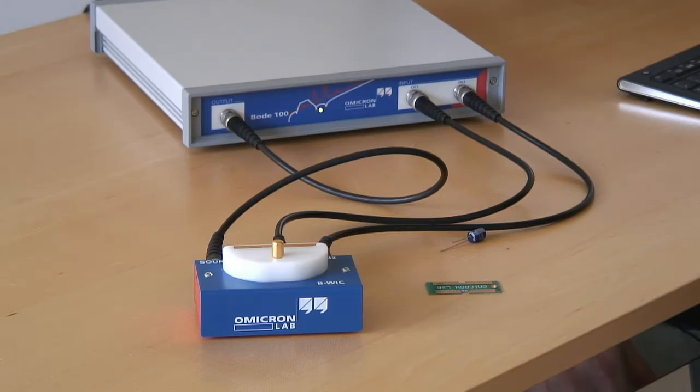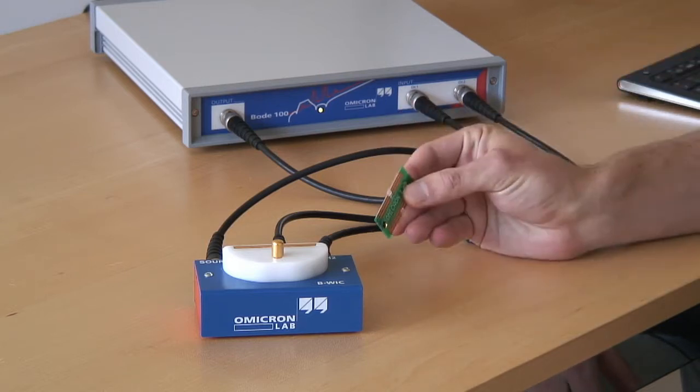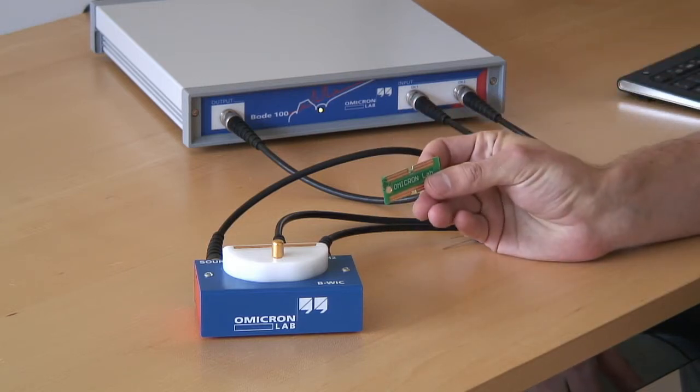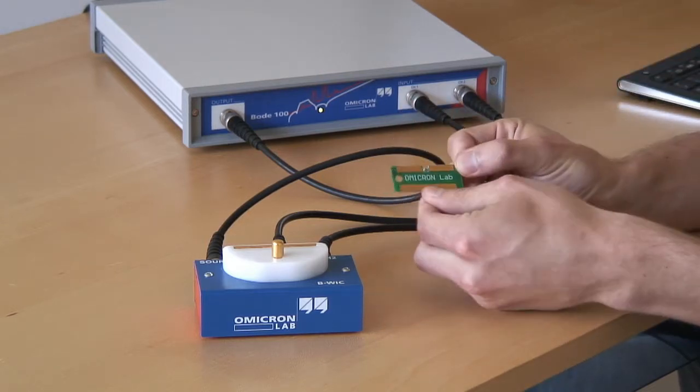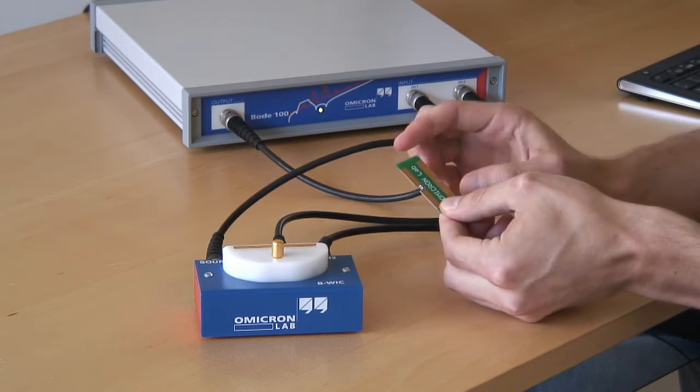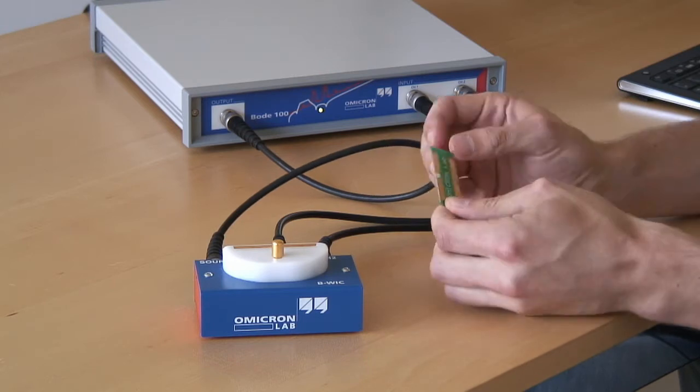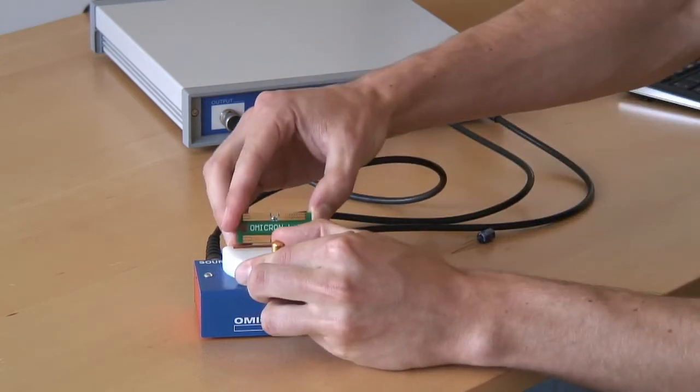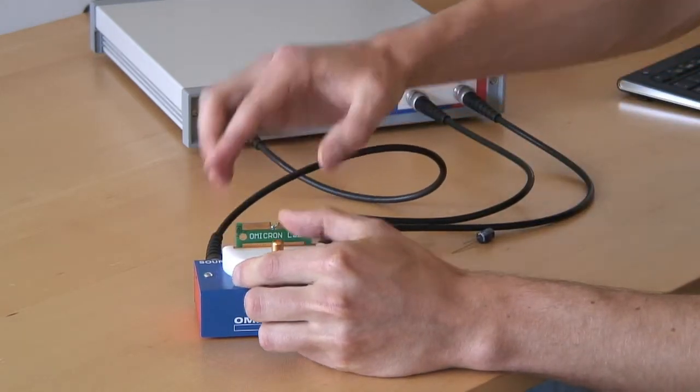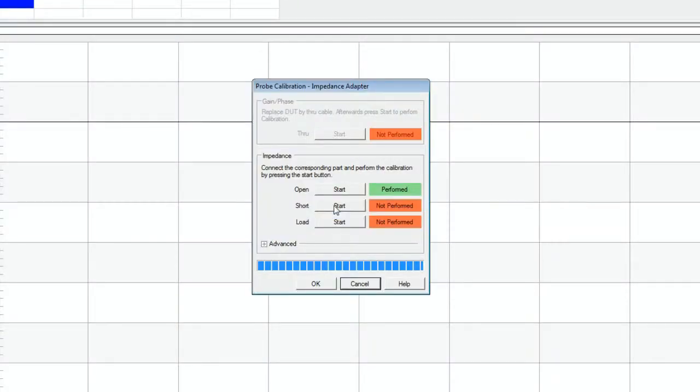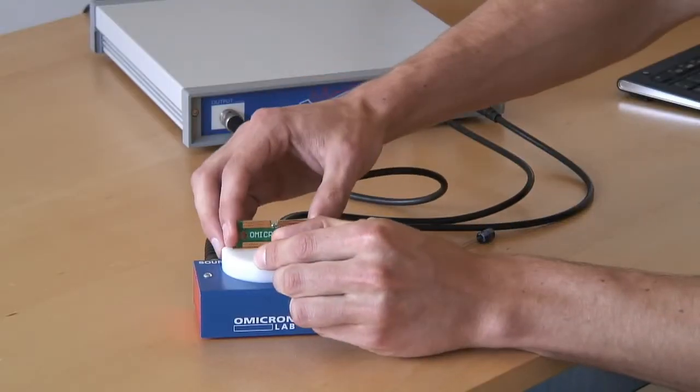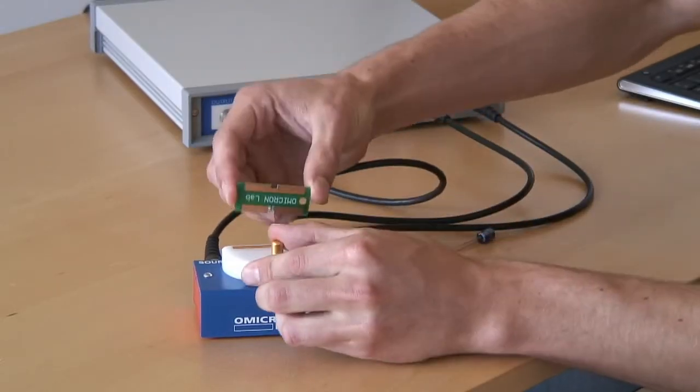For the short and load calibration, we have the calibration board that has a short and a known load. Therefore, we connect it for the short calibration and turn it for the load calibration.